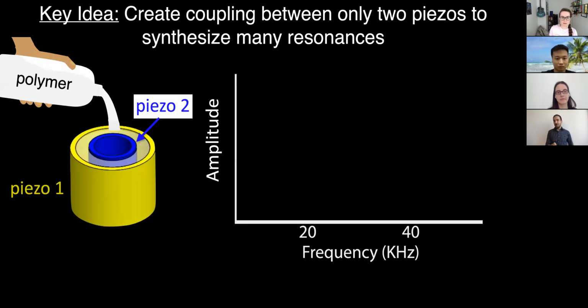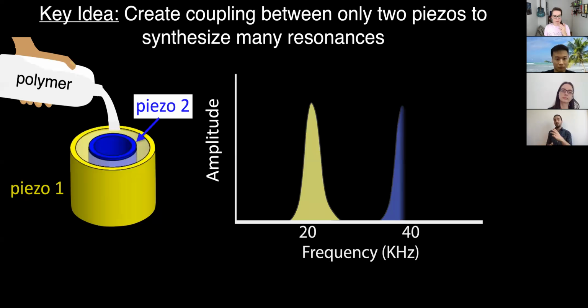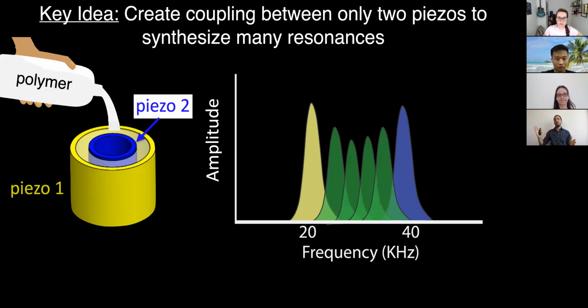When we plot the amplitude as a function of frequency, because the polymer is soft, it's a rubber-like material, the outer and the inner piezo are still able to vibrate at their original frequencies. So you get 20 kilohertz for the outer one, and 40 kilohertz for the inner one. But because we added the soft material that filled in the gap between the two piezos, we also created new constraints. And these new constraints result in new unnatural resonance modes. These unnatural resonance modes fill in the gap between the low and the high frequency. And by filling in these gaps, we're able to achieve a wide bandwidth.